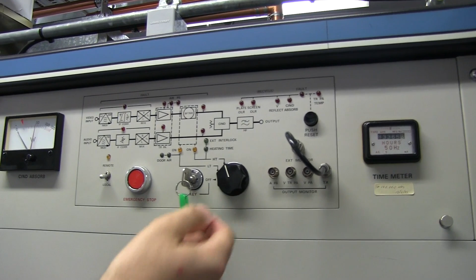So that would normally be in and the control key would be out, so that you can put it into the control panel and turn it on. So to actually get into the thing means turning it off, removing that key, and now this has been locked out. You'd put the control key down there, flick that off, HT is shorted, mains power is off, then you can take out the rear door key.